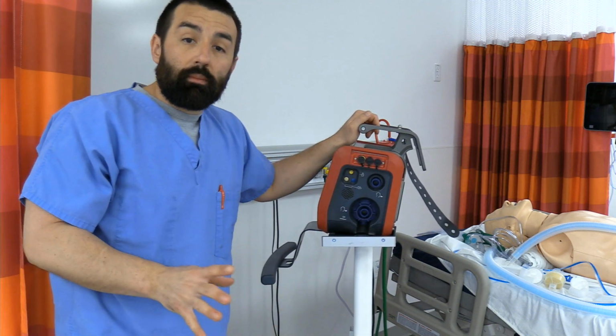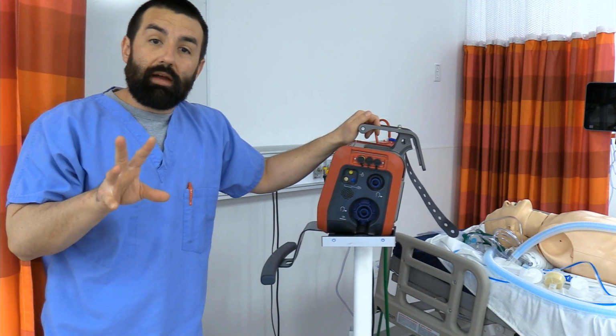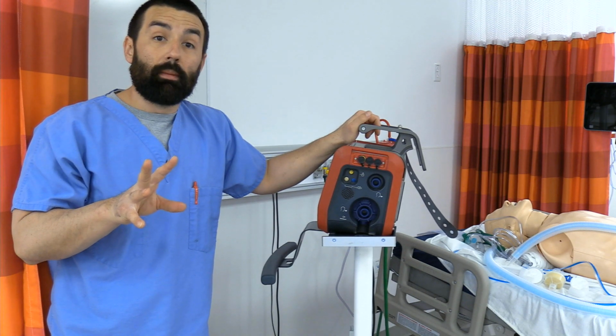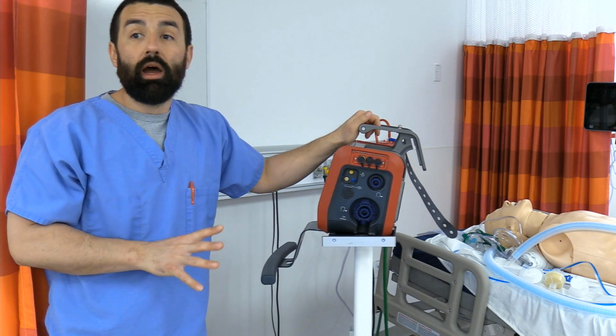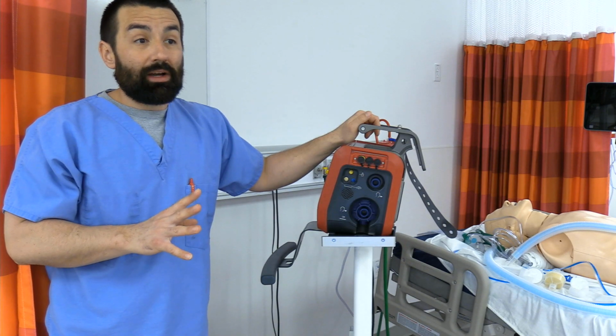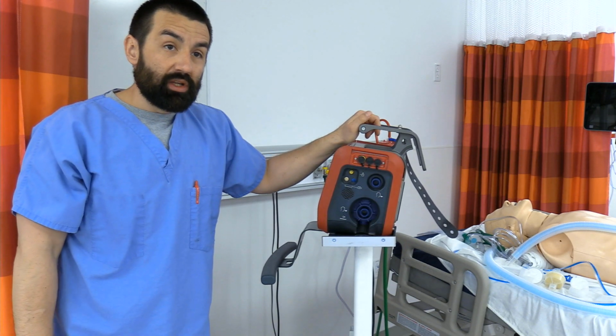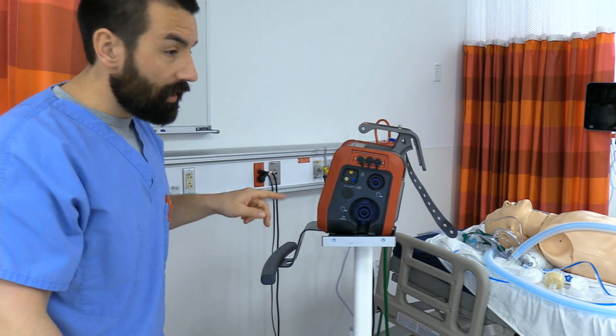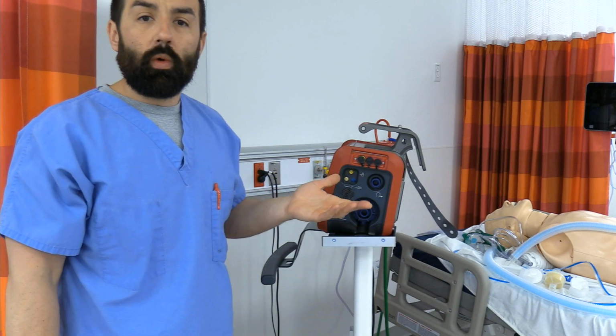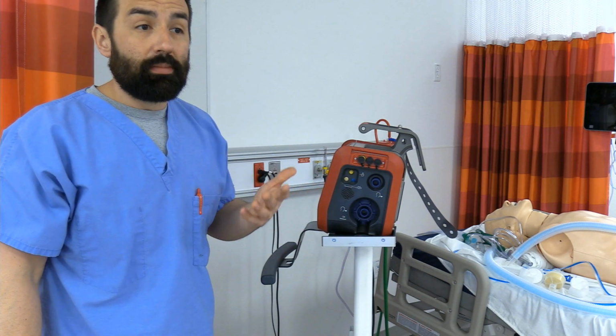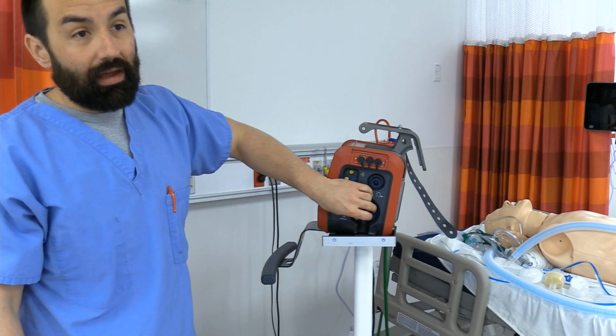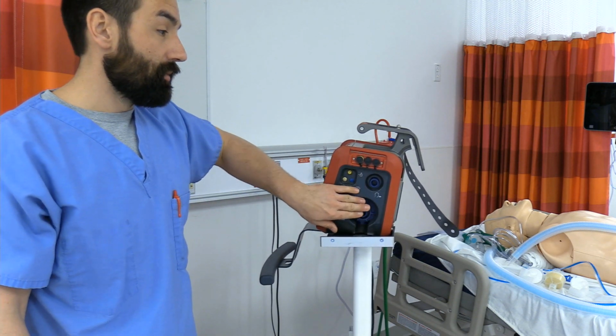All right, very, very important that you have this in properly, and you also have the exhalation diaphragm properly seated and you're using the right one. Otherwise, this ventilator is not going to work the way we need it to, and you're going to have some serious problems. As long as you're doing your pre-use check, which I'll show you how to do, you'd be well aware of any problems, but just keep in mind if you're having issues, a lot of times I always question, did somebody put this in correctly?